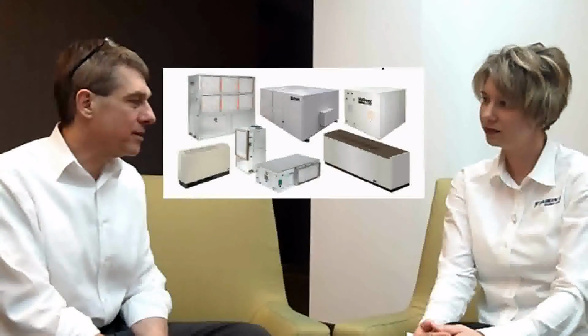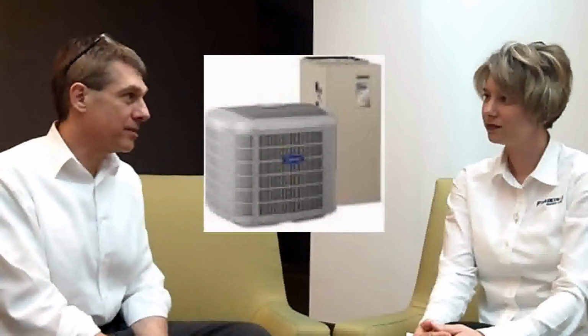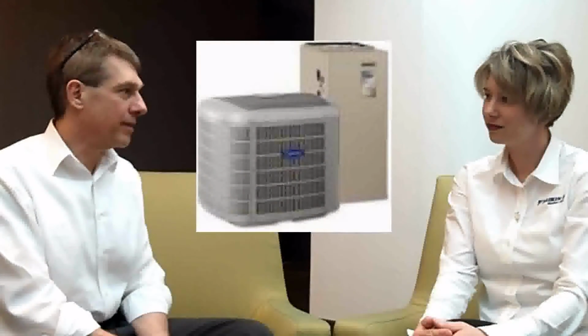What other systems did you consider for the Aloft? Well, we also considered cooling tower 3 and 4 pipe systems. We considered using standard split systems, and then of course the VRV systems. And in the overall scheme of things, the split systems were the least expensive initially, but some of the more wasteful on energy usage. VRV and the multiple pipe systems both had similar initial install, but the overall efficiency of the VRV made it the system of choice.